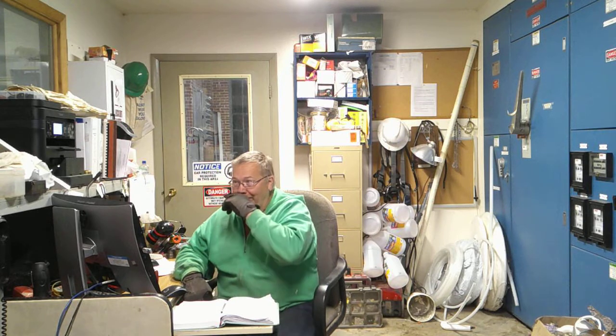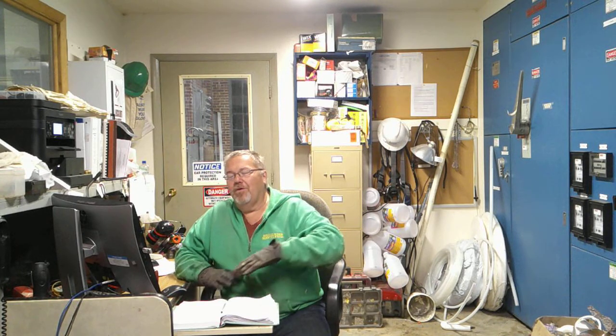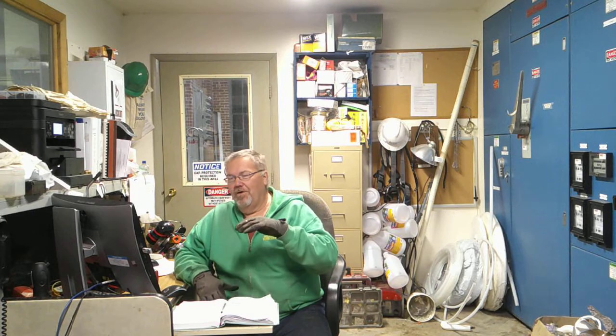The power dam this morning, we are a little bit higher than we were yesterday, which is a plus. We're still not to a level where we can reset. You heard me say that I can't reset the faults yet. We're within about nine-tenths of an inch of height that would get us to be able to at least reset and be able to turn on. That being said, we can't turn on because the gate's closed, so we're still letting the pond raise up. We're not controlling anything with the water at this point. So we need to get up to really the full pond level.